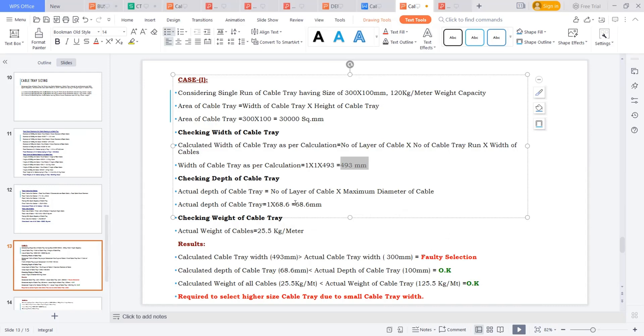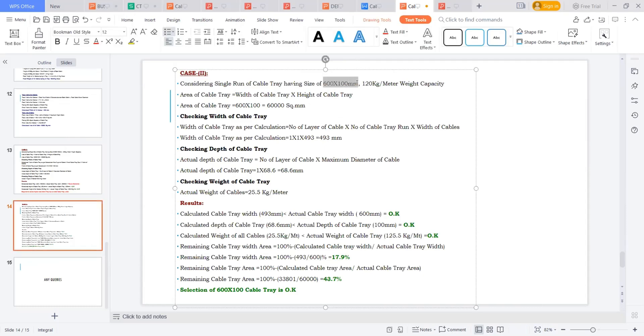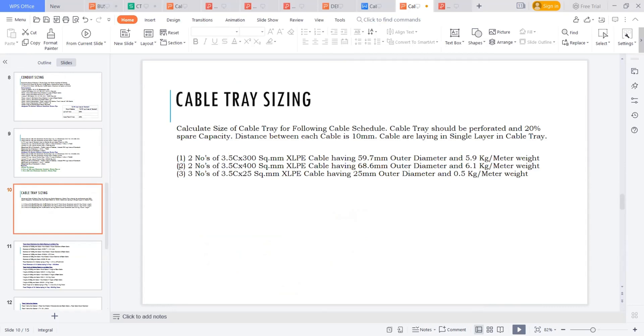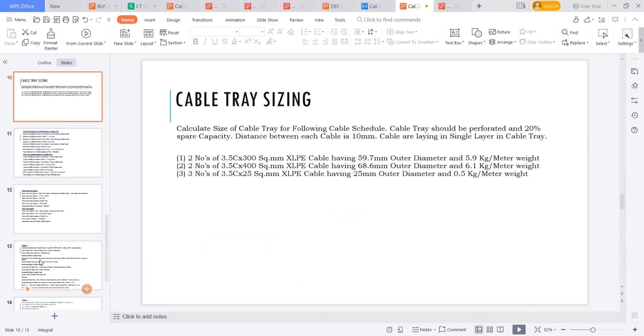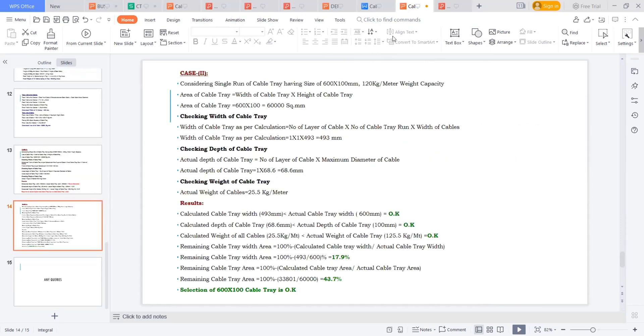The depth check: required depth is 68.6 mm versus the 100 mm available — sufficient. The weight check: 25.5 kg/m versus the 120 kg/m rating — sufficient. But width fails, so we go to the next option: a 600 × 100 mm cable tray. This is confirmed as suitable to carry the two 300 sq mm, two 400 sq mm, and three 25 sq mm cables. A 600 mm wide cable tray is selected.